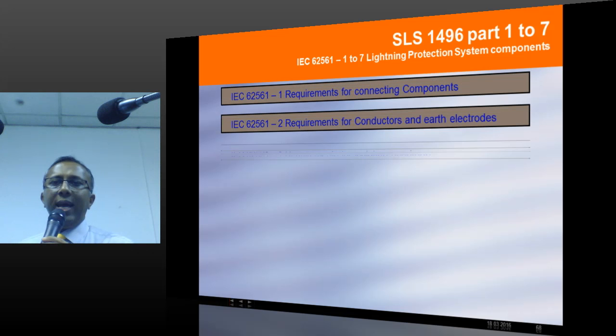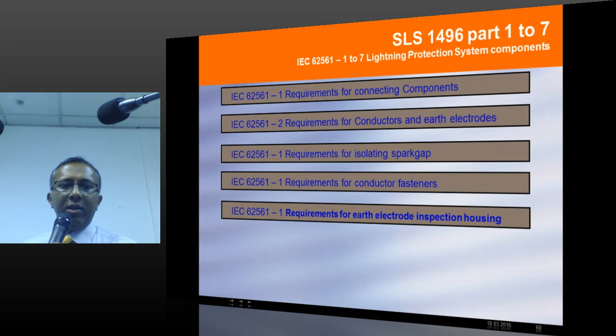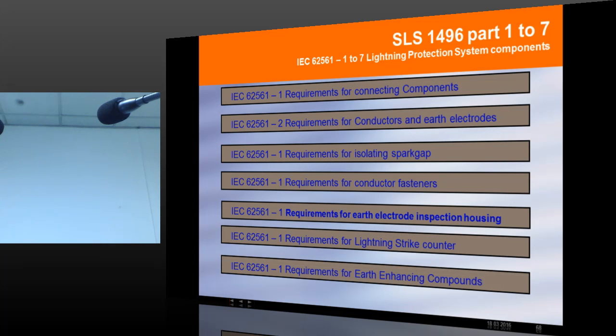SLS 1496 part 1 to 7. The standards which I was explaining so far, the first 4 standards, are explaining only the total protection as a whole. It is not talking about any components. The standard is okay with, for example, a round conductor, maybe 10 mm diameter and so on. But you need to check this particular standard for, for example, requirements of connecting components, requirements of conductors and earth electrodes. So these are the supplementary standards which need to be referred to for selecting a component.